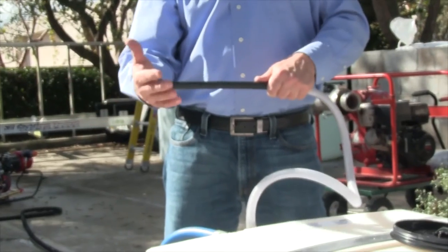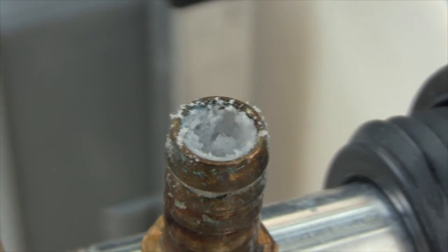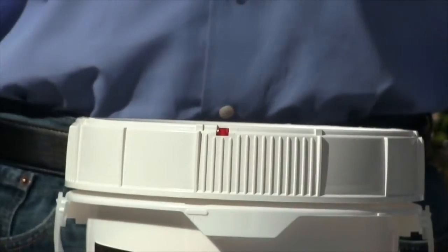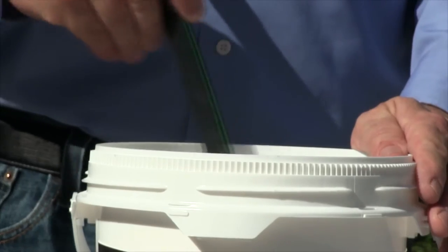Next, close the recirculation valve and open the eductor valve. Check for suction at the end of the eductor pickup tube. This is necessary to prevent water from traveling up the pickup tube and into the Fire Ice Shield bucket, which could potentially clog the system and prevent eduction.